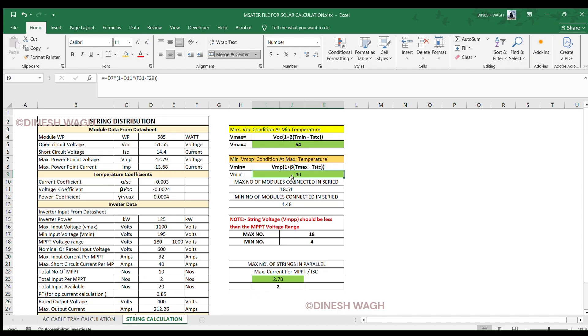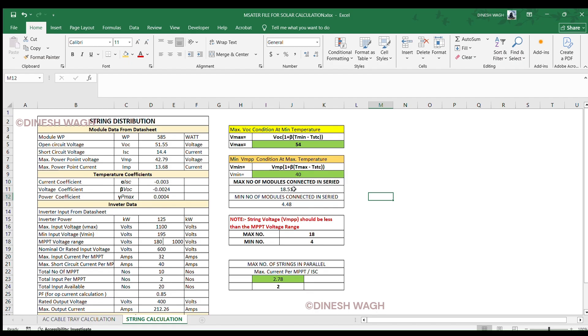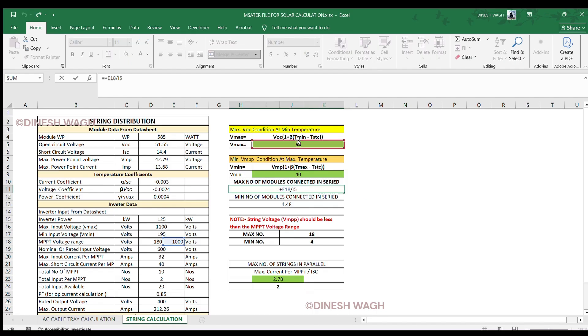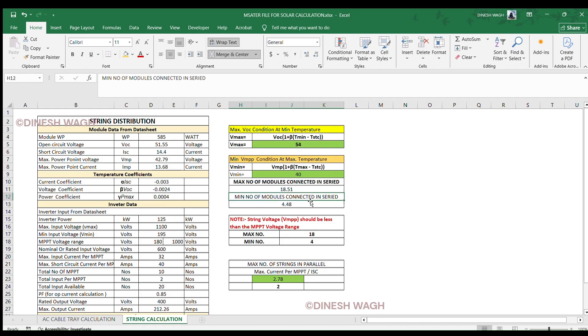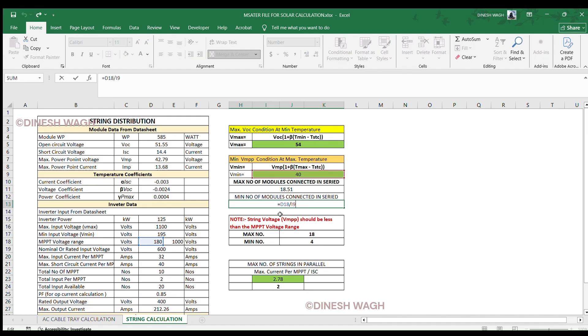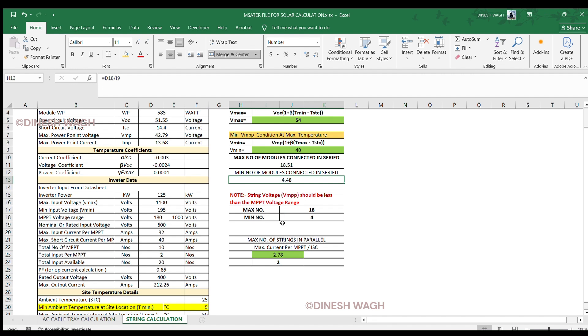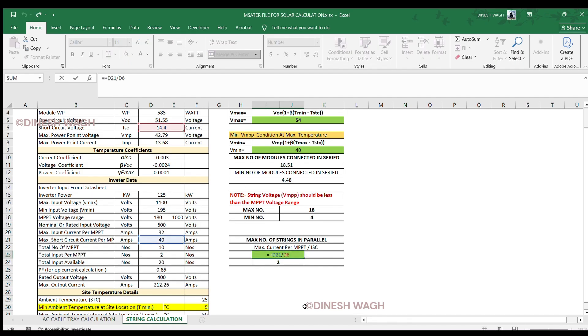In Part 5, we look at the series string limits — how many modules can be connected in series. Maximum modules in series: 1000 ÷ 54 = 18 modules. Minimum modules in series: 195 ÷ 40 = 4 modules. So we can safely connect 4 to 18 modules in series depending on the design. For parallel strings, current is the key factor. Maximum strings per MPPT: 40 A ÷ 14.4 A = 2.78, rounded down to 2 strings in parallel per MPPT.